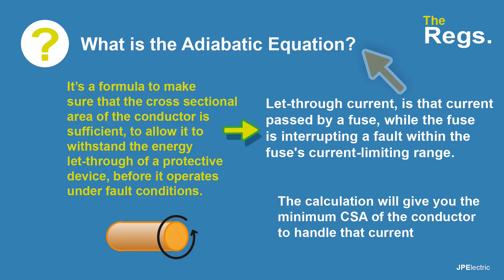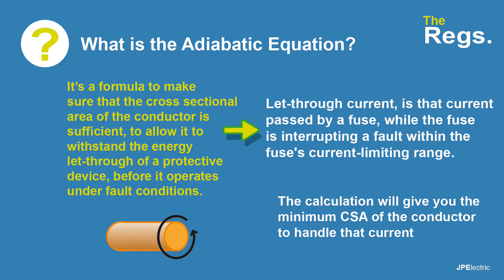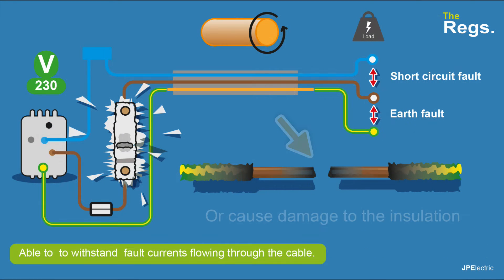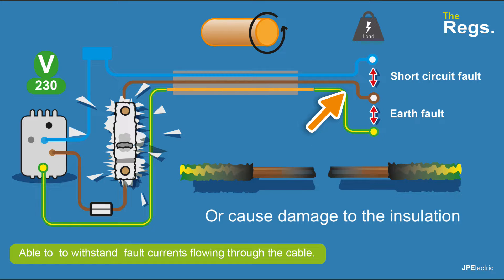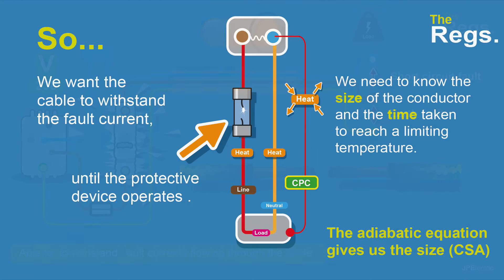So what is the adiabatic equation? It's a formula to make sure that the cross-sectional area of the conductor is sufficient to allow it to withstand the energy let-through of a protective device before that device operates under fault conditions. Basically, we want the cable to be big enough so it can handle fault currents. During a fault, you can get hundreds or thousands of amps flowing, and that can heat up the cable. If it heats up too much, that cable can snap, just like the fuse wire in a rewindable fuse. Your conductors for the installation can also heat up and break if they're incorrectly sized for any fault currents that may flow. So it's an important calculation.